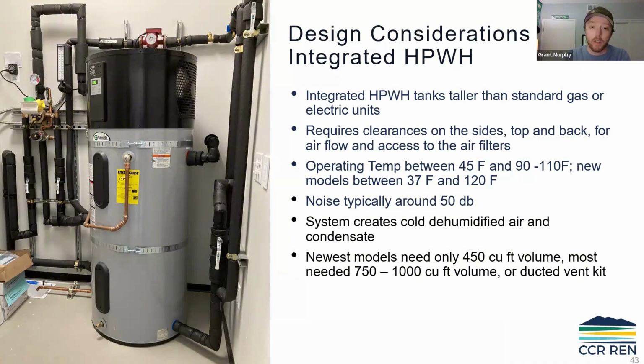Since then, four years ago, they've come down in the amount of volume required. You can see what Jennifer threw in, 450. So it depends on the specific make and model of the unit what that required volume is. They've come out with more duct kits, so you'll see more duct installations. We get a lot of questions on how to duct them, where the intake and exhaust. Can I just duct the exhaust? Can I just duct the intake? A lot of nuance, especially for a single family residence, where we're often replacing a tank unit, and it's trying to throw one of these things into the existing space of a gas tank unit that didn't require that volume.